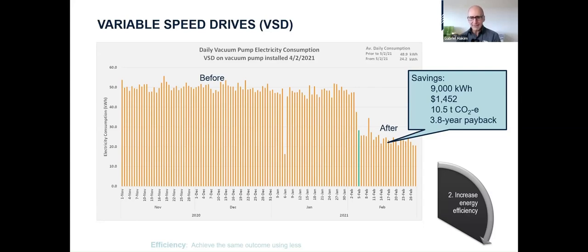So once again, less energy to achieve the same outcome. So very easy to get. Just a point in terms of scale of energy, how energy hungry vacuum pumps are: a water ring vacuum pump is the most energy hungry. The next one is the oil ring vacuum pump, and the lobe vacuum pump will be the least of the three types of vacuum pumps in terms of energy requirements. The good thing about the lobe vacuum pumps is you save on oil if you've got an oil ring vacuum.